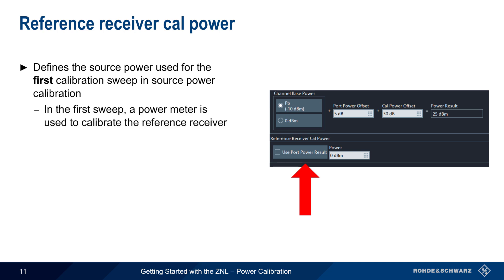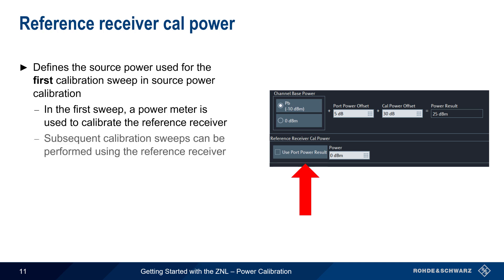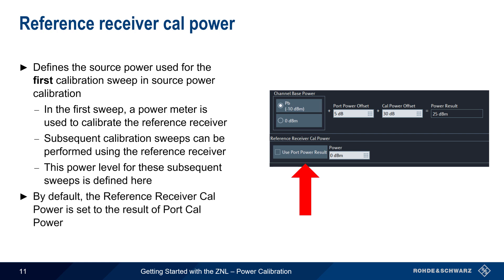Underneath the channel base power settings is Reference Receiver CalPower, which defines the source power used for the first calibration sweep in source power calibration. As we'll see later in this presentation, an RF power meter or sensor is used during this first calibration sweep to calibrate the Reference Receiver. However, subsequent calibration sweeps can be performed using only the Reference Receiver, and Reference Receiver CalPower defines the power level for these subsequent sweeps. By default, the Reference Receiver calibration power is set to the result of the Port Power calibration.